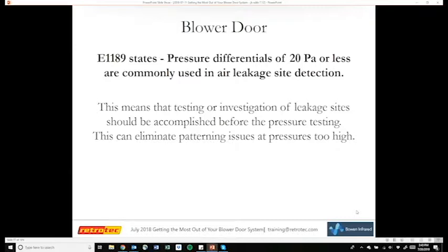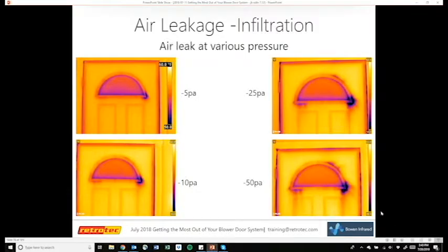Now, Sam brought up referencing 50 pascals or minus 50 pascals as a pressure test standard, which is valid. What we're saying here is that if I'm trying to do thermography detection of a leakage point, I can do that with a lot less than 50 pascals. I can do it as low as 5 pascals, and some of the imagery that I have will reinforce that. And why I say try and do it with less pressure is a typical building wouldn't have a 50 pascal pressure within it or on it, so a normal air leak would be typical of a 5 Pa or a minus 10 Pa.